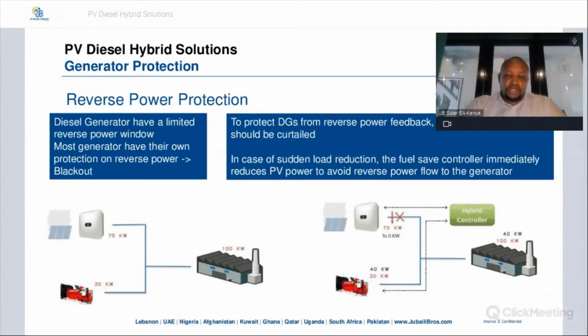Next is reverse power protection. Reverse power is when power goes back to the source, in this case, when power goes back to the generator. Most generators have a limited reverse power window, and others will have their own protection on reverse power. So to prevent reverse power, the controller will cut off feedback from either the grid or the solar or from the battery, and reduce the power that is coming from those other sources so that they are not fed back into the generator. This can be through curtailing of the PV system or reducing the power from those other sources.